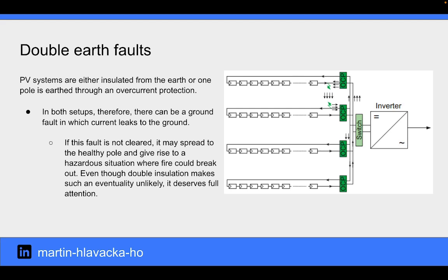PV systems are either insulated from the earth or one pole is earthed through an overcurrent protection. In both setups, therefore, there can be a ground fault in which current leaks to the ground. If this fault is not cleared, it may spread to the healthy pole and give rise to a hazardous situation where fire could break out. Even though double insulation makes such an eventuality unlikely, it deserves full attention.